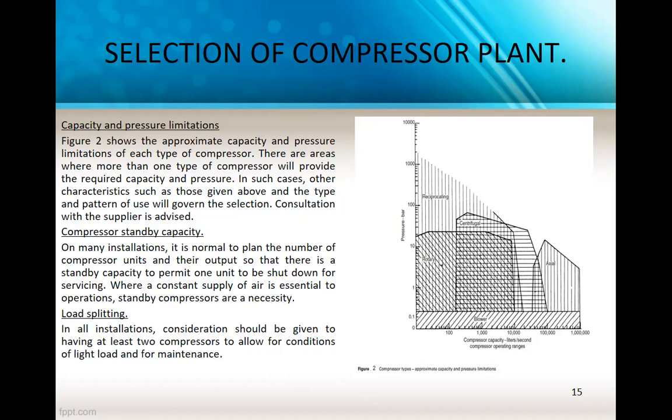Okay. So, load splitting, in all installations, consideration should be given to have at least 2 compressors to allow for conditions of light load and for maintenance. So, yan. Minimum of 2. At least 2.